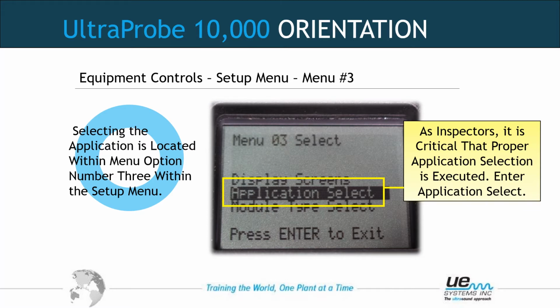Menu item number 3, application select. This is important that we choose the correct application when we are route based in our inspection. If we are troubleshooting, it does not matter which application it is tuned to. This deals with loading the route back to the software, as the name of the application, bearing, valve, electrical, is part of the nomenclature of the route. Also for input data, as far as parameter information around what we are testing. That input data would change if it was electrical versus bearing.